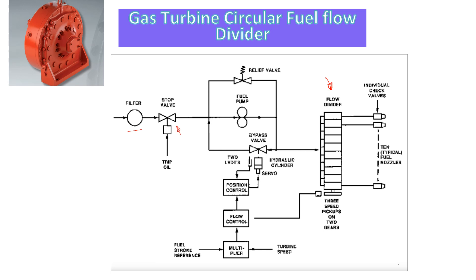As the name suggests, this is equipment where only one liquid fuel flow is coming in. For a Frame 6 machine, there are typically 10 outputs. You may see 11 or 12 physical outputs on your flow divider in the field, but one is always spare. The purpose of the flow divider is to divide fuel in equal quantities so there is uniform combustion in all 10 combustion chambers, with minimum fuel spread and exhaust spread.